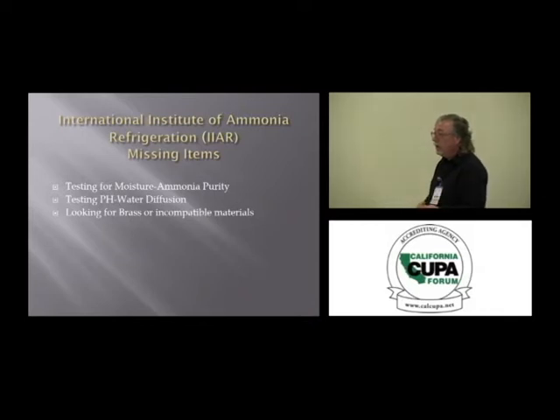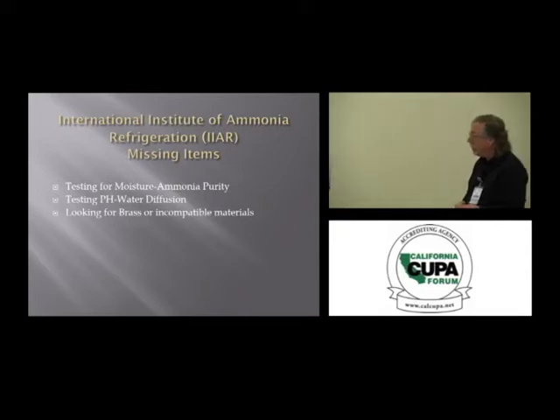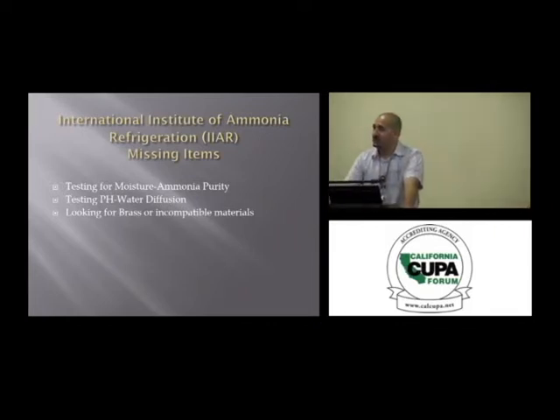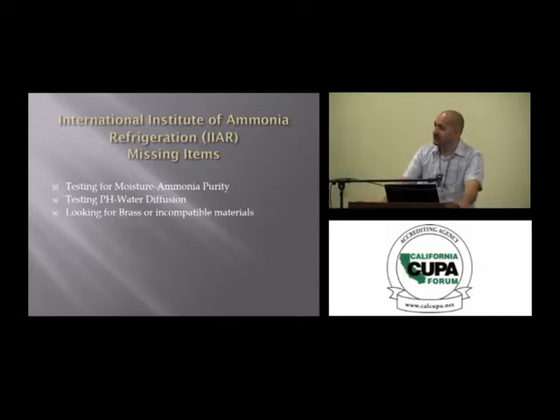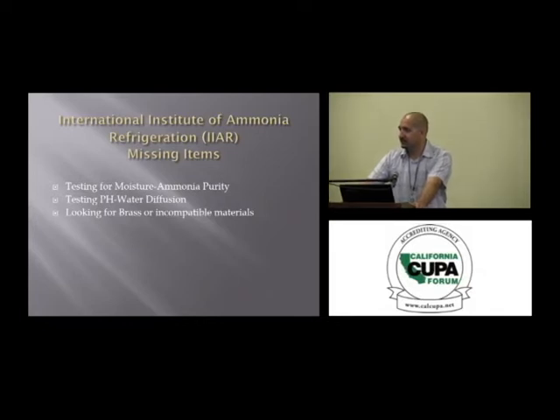I think we're asking whether or not you need to do testing on the pipe to make sure that there hasn't been parts of the system that has had unacceptable corrosion. So how do you make sure that the system integrity wasn't compromised? Due to the moisture? Yeah. That is going to be internally, and that's going to be hard to see. And I hate to say it, but if I see any outside corrosion, it's very easy to detect and perform non-destructive testing to ensure the pipe. But go ahead, I'm sorry. IIAR has no internal kind of a requirement.